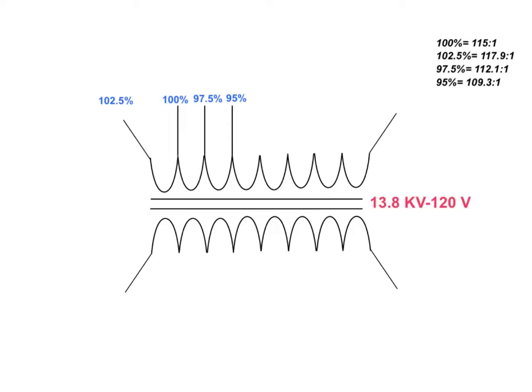So again, just to recap because it's very important: We take the 100% ratio first. We get that by going 13,800 divided by 120 to get the 115 to 1 turns ratio. Then we base these other taps off of that 100% tap. So I go 115 times 1.025 to get 117.9. I take 115 times 0.975 to get 112.1, and I take 115 times 0.95 to get 109.3.